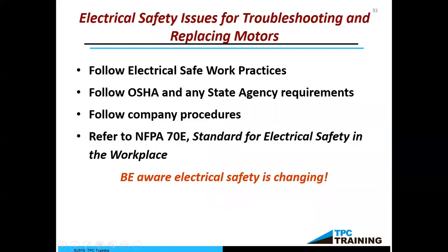I just want to say this, that we do want to take a look at safety, because we want to be safe when we're doing all of this. So we want to make sure we understand about OSHA 1910, which is general industry. If we're in the construction trade, it would be 1926. Whatever our company says about safety, the standard for electrical safety here in the U.S., of course, is NFPA 70E. So if we're tracing voltage, we should know what the incident energy is, we should know what the voltage level is, and protect ourselves from those two hazards.